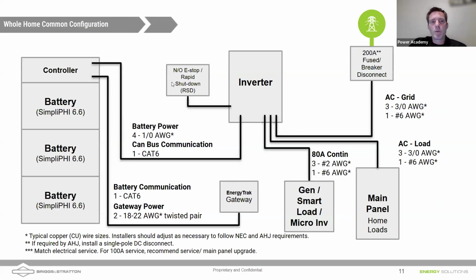Wiring here, again, we have that rapid shutdown. We've got our DC connection to the inverter. Also available for the 6.6 battery. It is a closed loop communicating battery. With the gateway, we can monitor individual modules. So we can look at the temperature inside individual modules. We can look at how those individual modules are doing health-wise. And so for larger systems, we're getting customers wanting to use Energy Trak to do that. We can also see some of that battery information in the inverter. So we're running a communications wire between the controller and the inverter as well. So that's your Ethernet cable here.